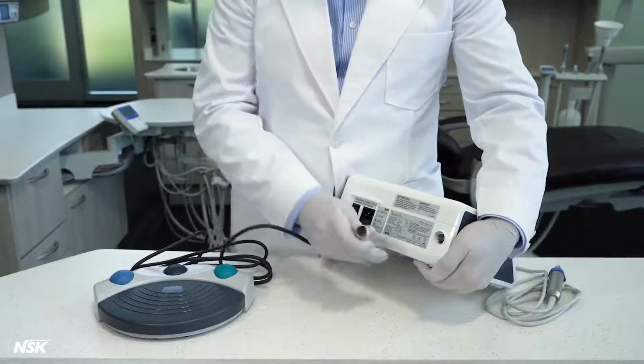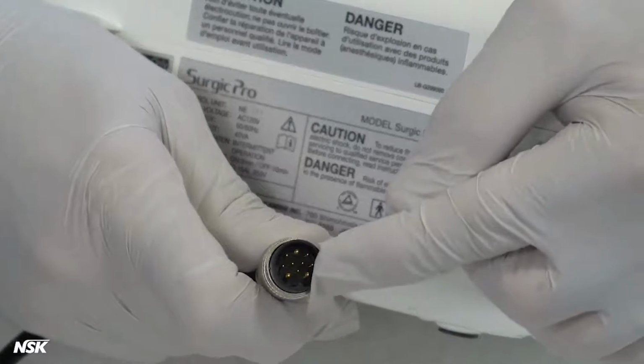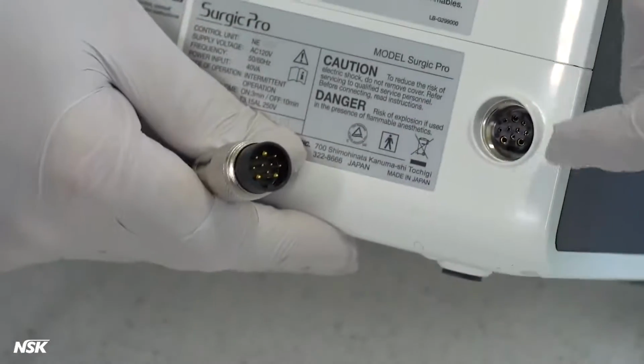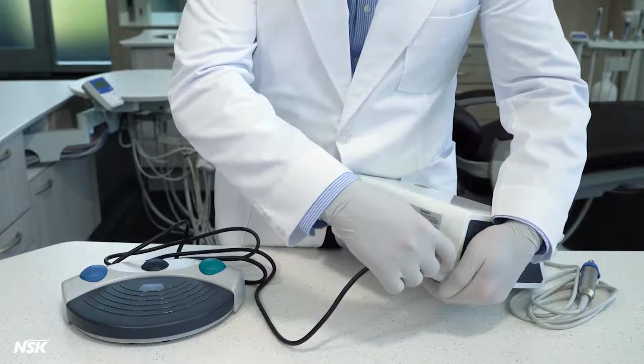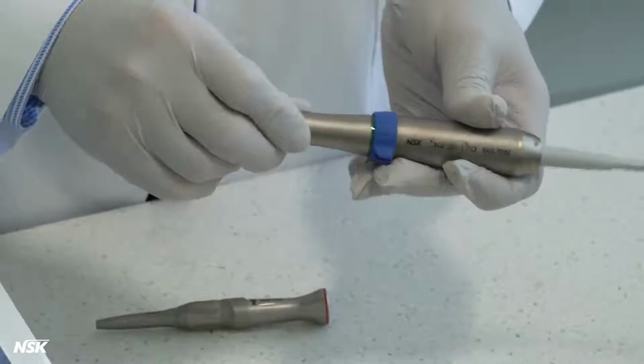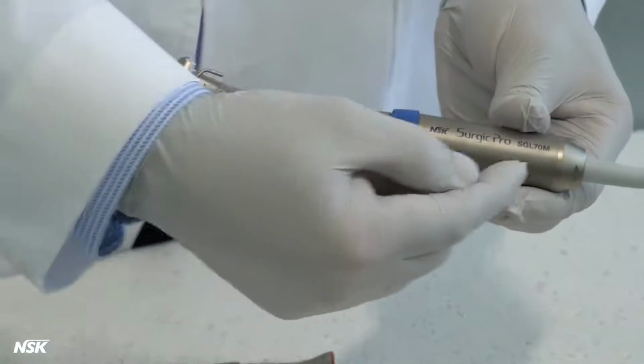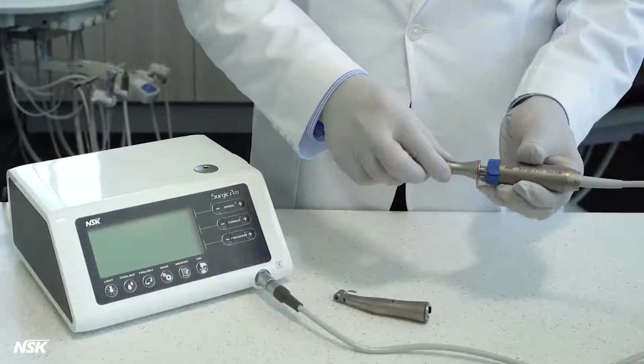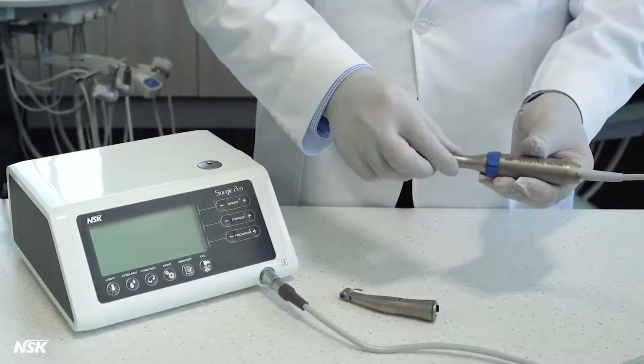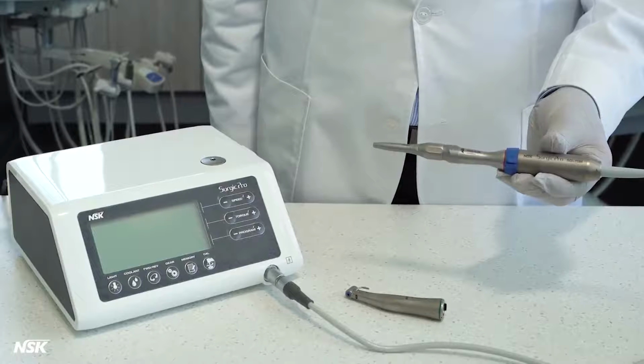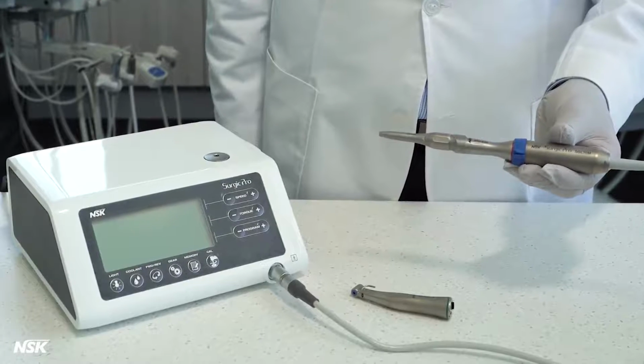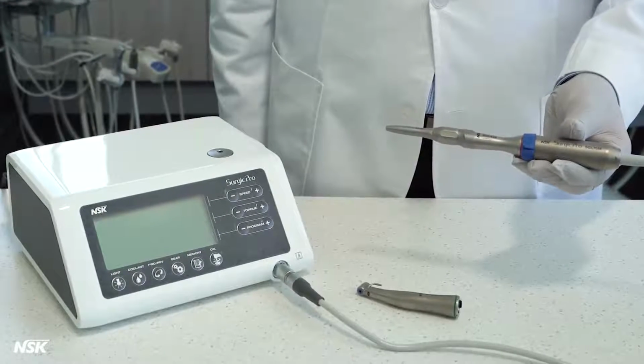Next, connect the foot control cord using the guide pin located at the bottom of the connector, which is at the back of the unit. Tighten the lock nut to screw and secure the connection. Insert the attachment into the motor and twist until it locks in place. Non-optic attachments do not need to be twisted to be locked in. However, microsurgery handpieces will need to be twisted on non-optic motors to be locked in place.